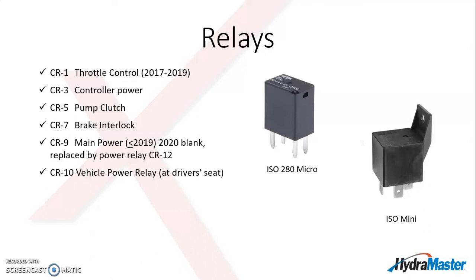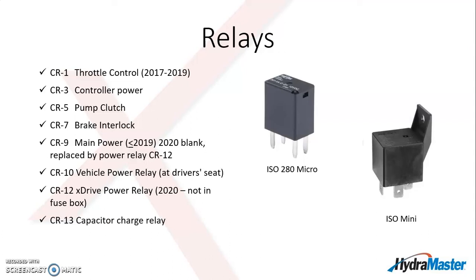Relay number 10 is that vehicle power relay talked about down at the battery, which switches the battery power based on the ignition. That relay is mounted down next to the battery, as close to that customer connection point as we can. And then CR12 is the new main power relay. CR13, so relay number 13, is the relay that's in the capacitor pack. That's what turns the charging circuit off and on.